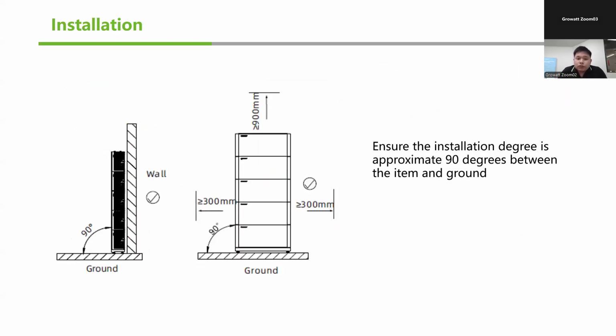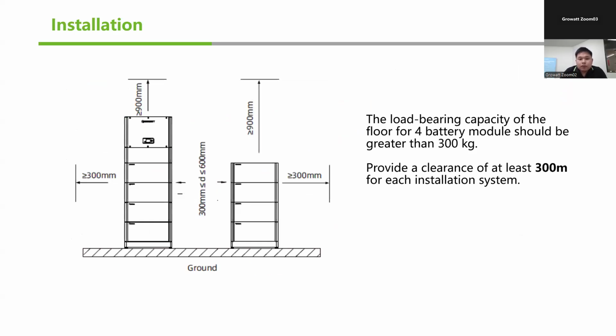Now, it's very important to make sure that the system is installed at an installation angle of 90 degrees against the ground. This allows enough space and makes sure that the system is well aligned to the surface. In addition, enough room must be provided for this installation to happen, so make sure to find a space with enough room. If the customer has more than 4 batteries, they must have at least 300 millimeters between the inverter system and the batteries. And depending on the load itself, make sure that this is installed on ground that can withstand up to 300 kilograms of weight.